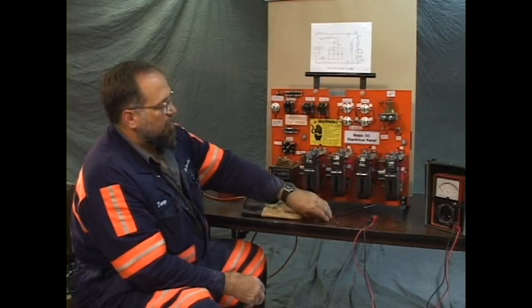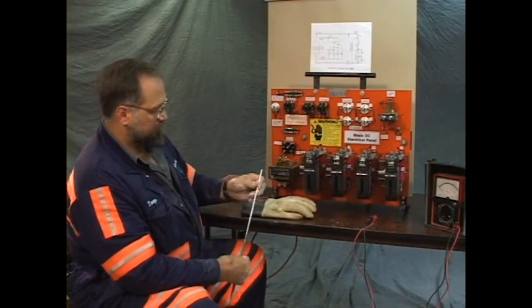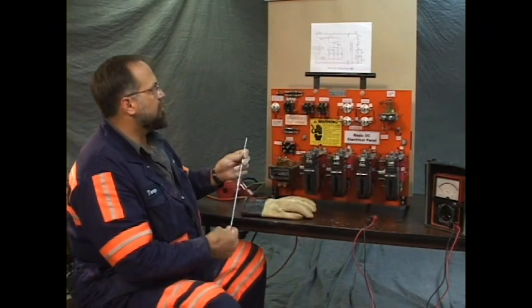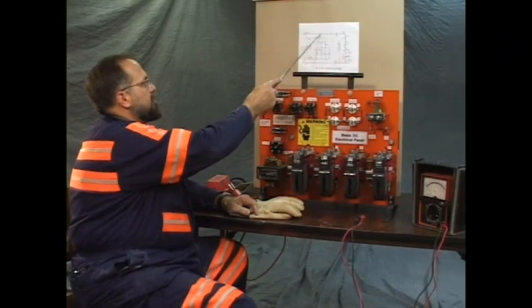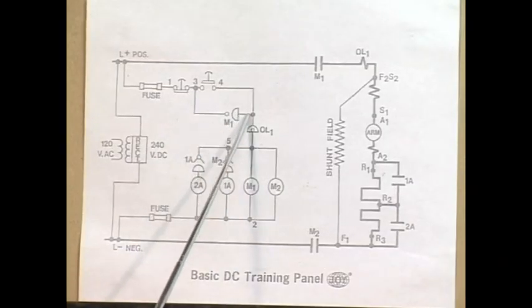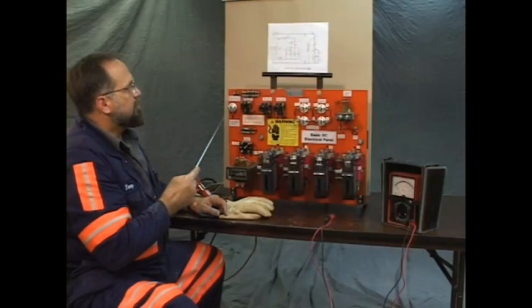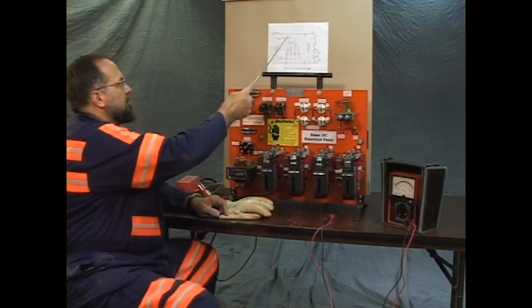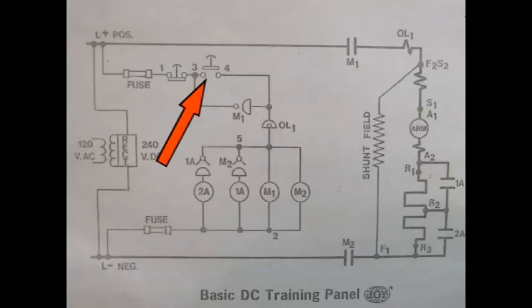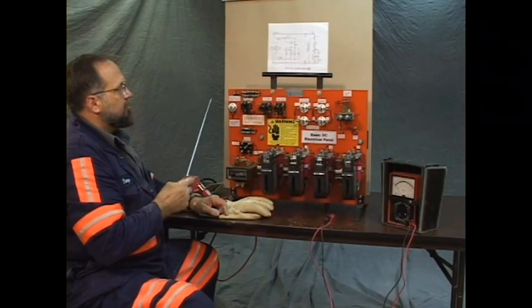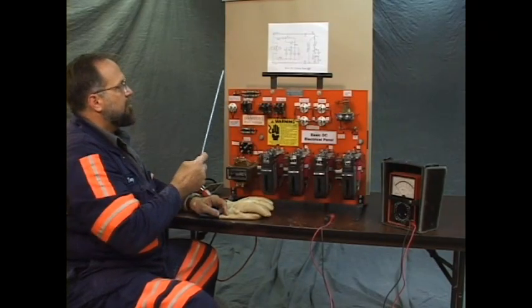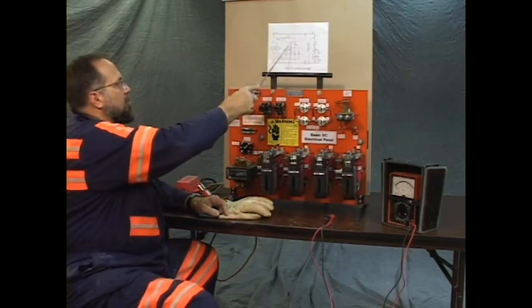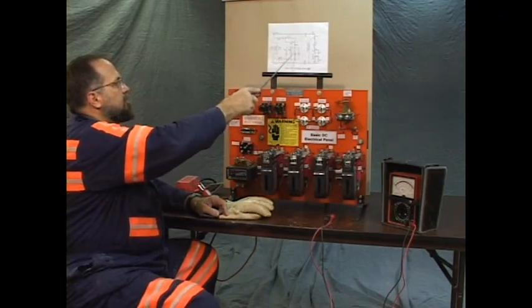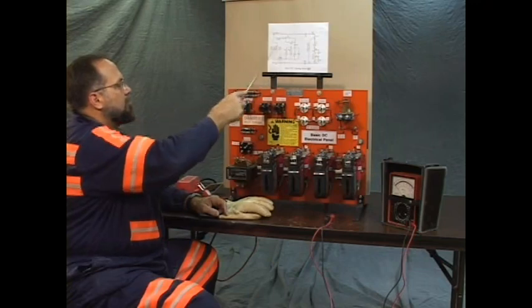Now, we spoke of the holding circuit. The holding circuit is part of the control that's in this portion of the print. As you can see, the components involved, there are two components, the start switch and the M1 mercury tube. The holding circuit is made up of those. The M1 mercury tube is actuated as an auxiliary device on the M1 contactor coil.